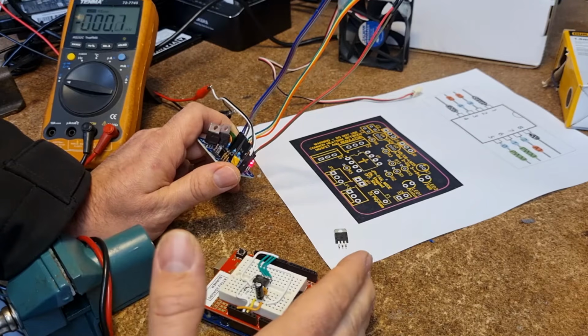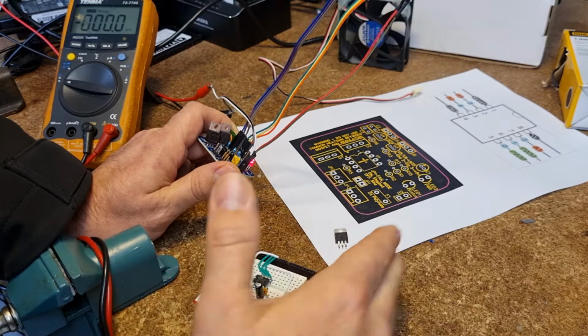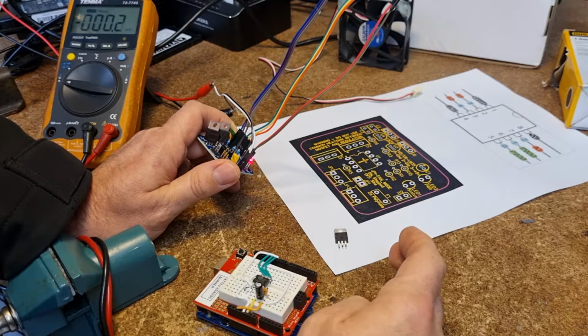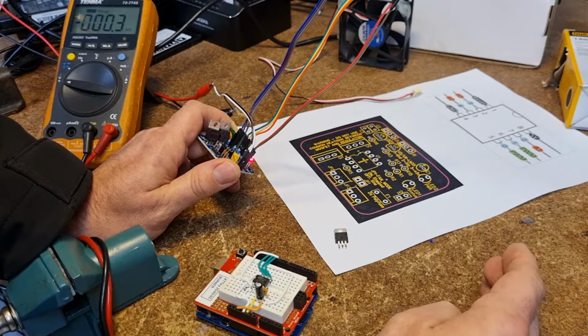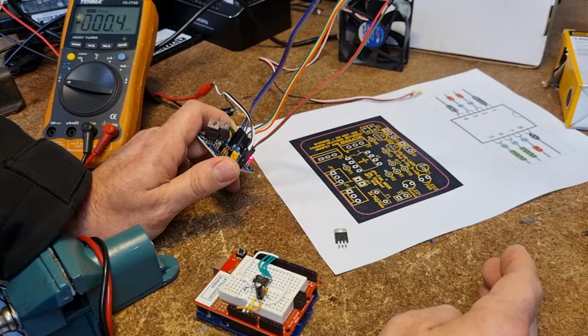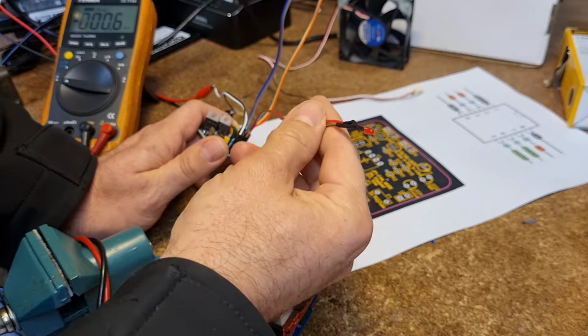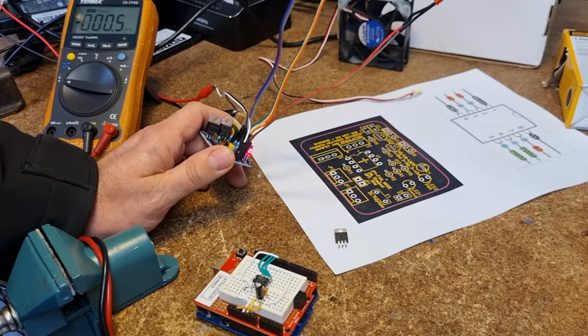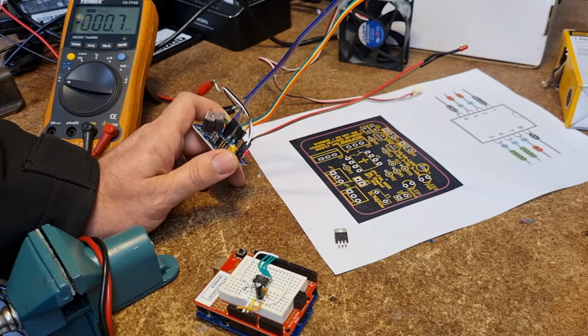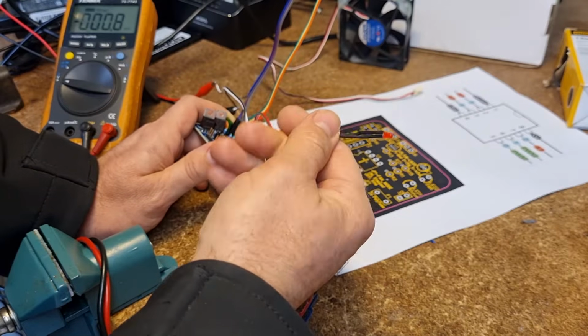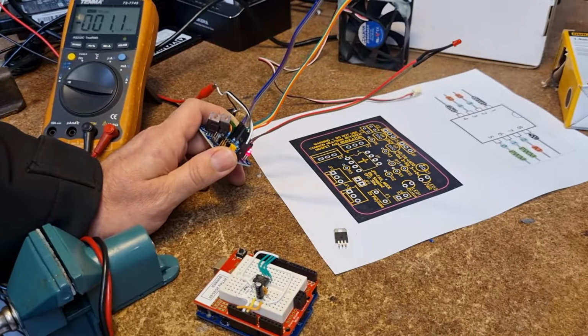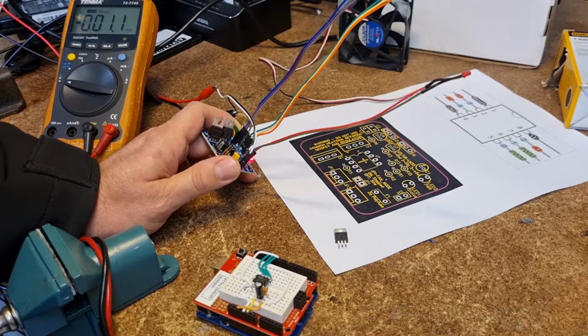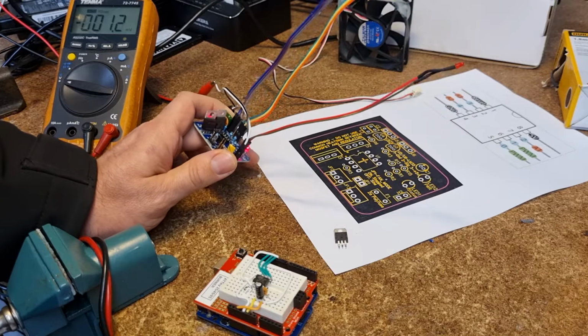Basically what this thing does: at around 40 degrees, if it's on stepped mode, between 40 and 50 degrees it will run the fan at 50%. Between 50 and 60 degrees it will run the fan at 100%. And if the temperature goes over 60 degrees, I've got a status LED that will flash a specific sequence. It also has power-on diagnostics, so the LED will tell you if either of the temperature sensors have a problem, are out of range, or not connected. It should be pretty good.